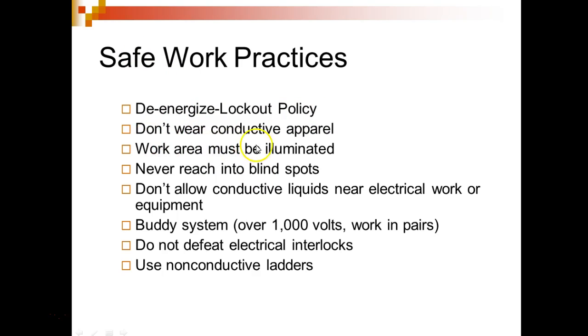De-energized lockout policy. Don't wear conductive apparel. Work in an area with good illumination, and we've got great illumination in this classroom. Never reach into blind spots. Don't allow conductive liquids near electrical work. Buddy system, which means if you work over 1,000 volts, you're supposed to work with at least 2 people, right? At US Steel, it was 500 volts, so if we ever worked on over 500 volts, we had to work with 2 people. Do not defeat electrical interlocks, and use non-conductive ladders.